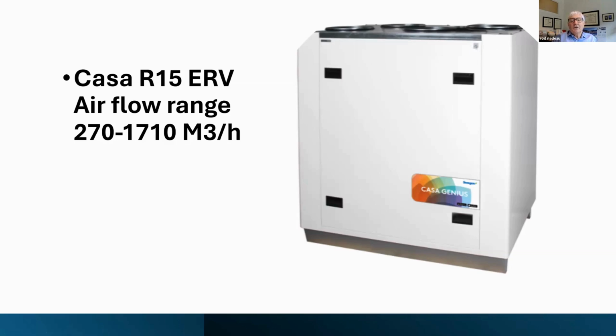And since the cooling load is greater than the heating load, the ERV is sized using its maximum airflow rate for boost cooling, which will only be needed during a heat wave. The ventilation rate can accommodate 80% of the cooling. The ERV is now running at an easy 60% of its rated capacity, 99% of the year.